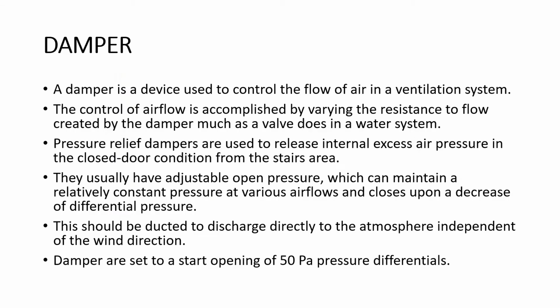Damper. Move on to damper. What exactly is a damper? A damper is a device used to control the flow of air in a ventilation system. The control of airflow is accomplished by varying the resistance to flow created by the damper, much as a valve does in a water system.